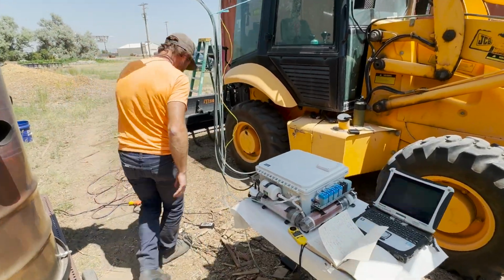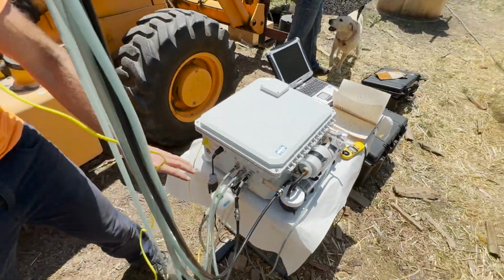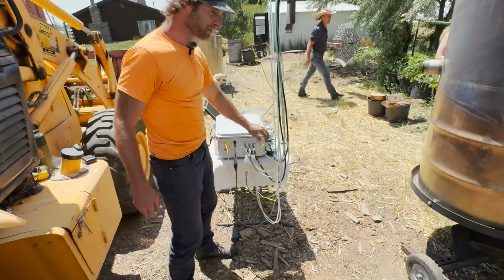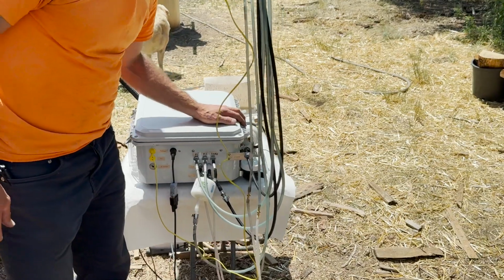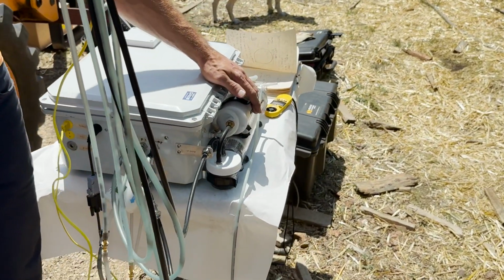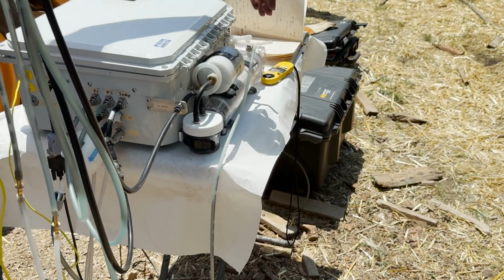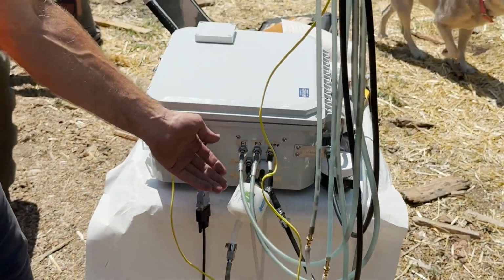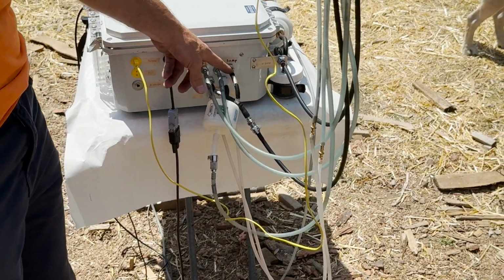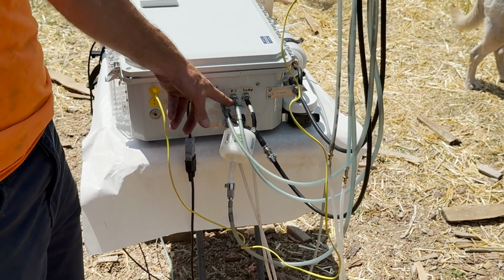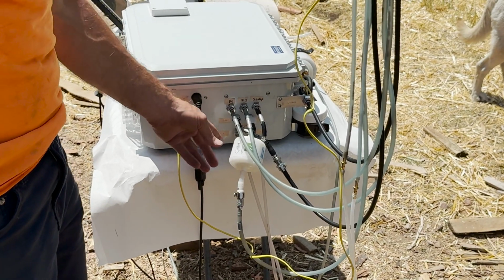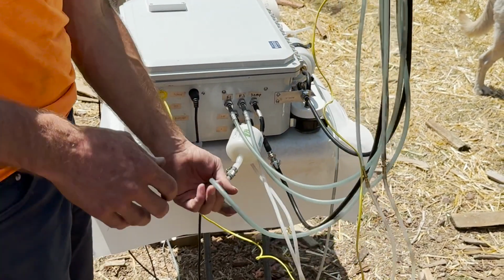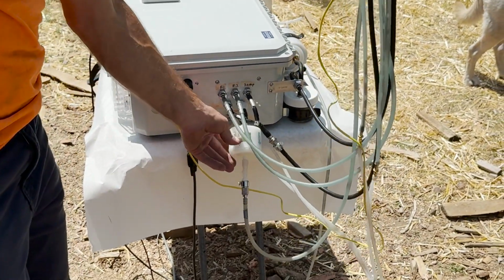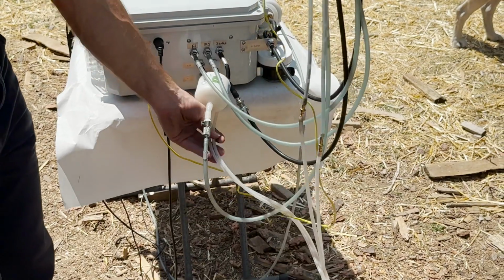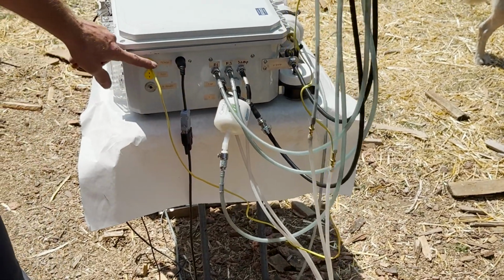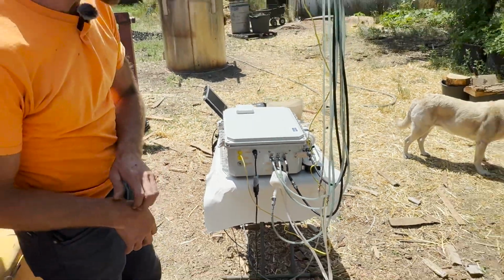And so coming around to see how the sensor box works. All the sample lines are coming in here. We have an undiluted sample line that's coming straight from the probe. It goes into a water trap, then to a HEPA filter, and then to a desiccator to dry the sample before it goes into the instrument. And then we have these diluted lines also. The sample goes into the particulate matter sensor, and there's two filters. We also have the dilution air that's being pushed out to the probe to mix with the sample. And down at the bottom, we have these two pressure lines that are measuring the differential pressure from the pitot tube, and a thermocouple to measure the temperature in the stack.